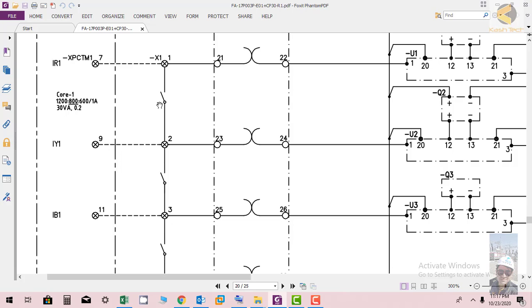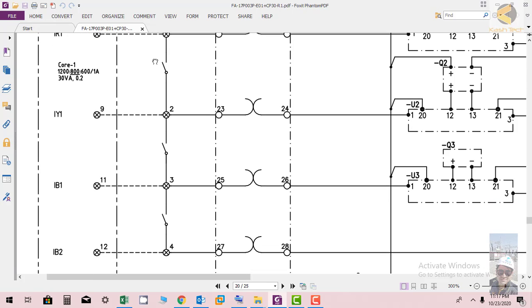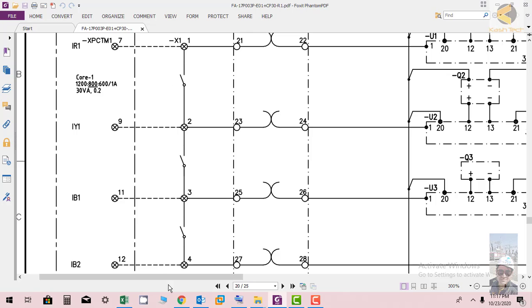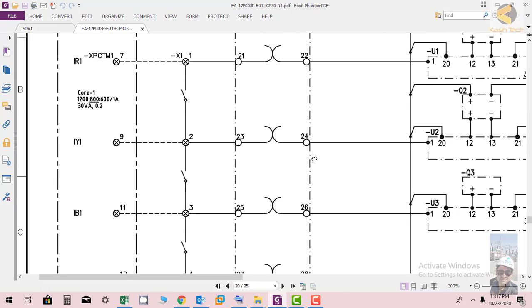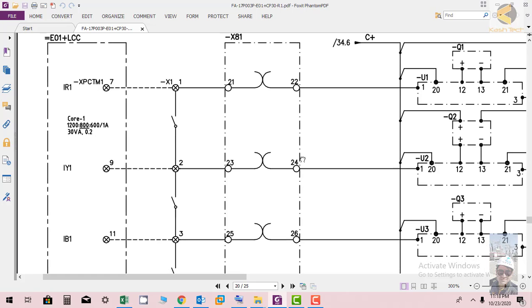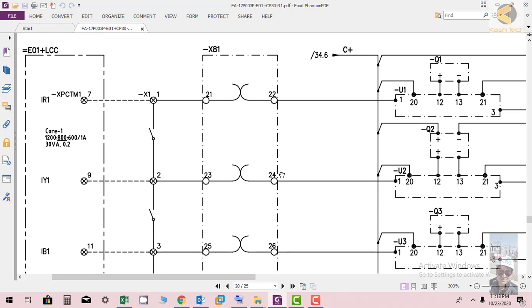You can see CT red phase, yellow phase, blue phase and the neutral coming. X1 is basically the shorting link. X81 is basically the test block. If you want to do testing, you have to insert test block in and it will isolate terminals.